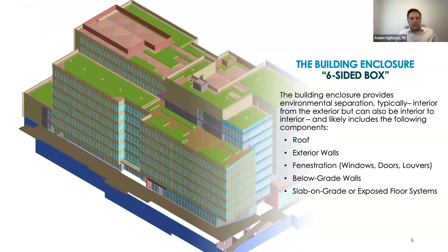When I talk about whole building, it's basically the balloon that is the whole building. So it's that outer surface area that is separating exterior from interior environments. We literally are pressurizing the entire building at one time. Doesn't matter the size, the concept's the same. We're trying to create the same pressure difference across all six sides of the box of the building. So exterior walls, roofing, your slab on grade, or you might have a podium condition where you've got a slab over parking level, that would be considered part of that enclosure. So really just testing that air boundary where we're conditioning and where we're not conditioning. We want to make sure that in the conditioned space, we're not losing that energy that we're using to cool or heat the building.